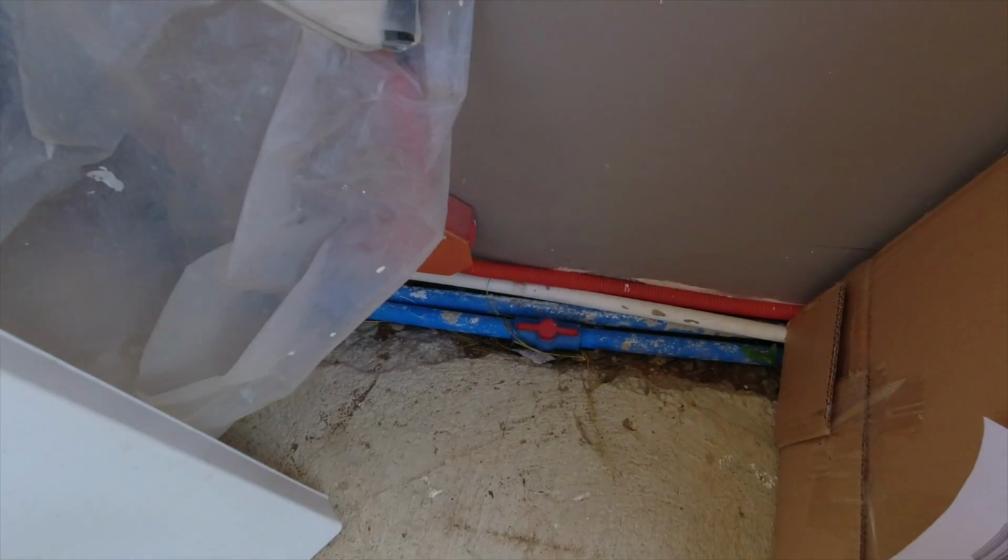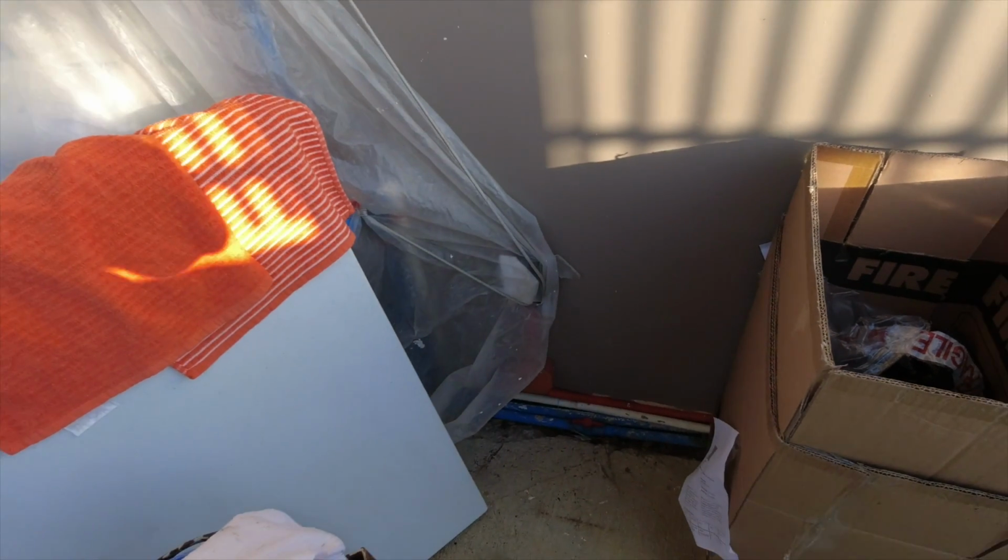So what we did is eliminate the pressure tank issue or motor issue, and we don't have a problem there. We double checked it, and we put a shutoff valve right there. This one right here. That's the pipe that goes to our bathroom downstairs and the garden faucet, like the side wall faucet. I don't know what you call that, but we could shut off that valve, and that's when we noticed that the motor stopped.